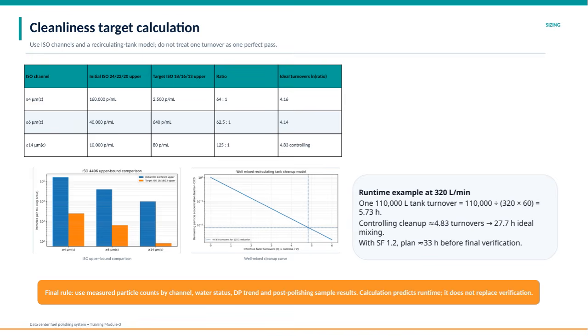about 4.83 turnover cycles. The example runtime calculation assumes a flow rate of 320 liters per minute through a 110,000-liter tank. One tank turnover takes roughly 5.73 hours. Given that effective cleanup requires approximately 4.83 turnovers, the ideal runtime comes to nearly 28 hours. When factoring in a safety factor of 1.2, the planned runtime before final verification extends to around 33 hours. Finally, remember the key rule. Always use actual measured particle counts by channel, assess water status and differential pressure trends, and consider post-polishing sample results.